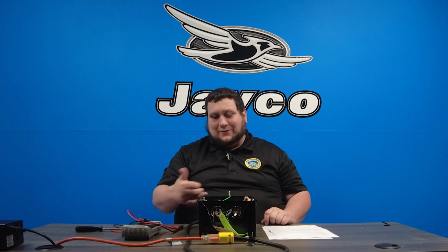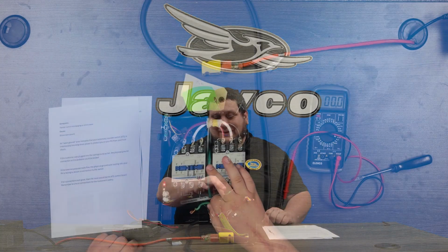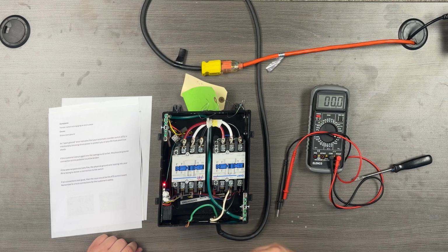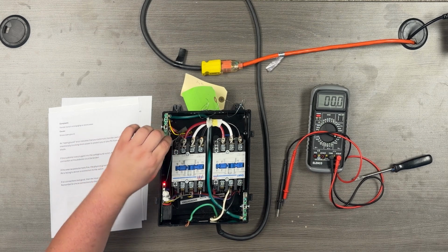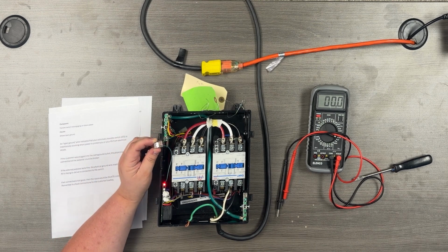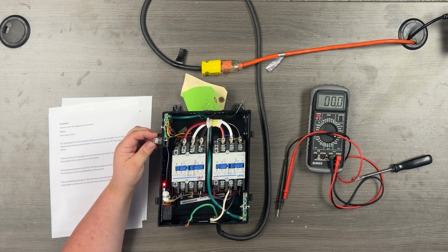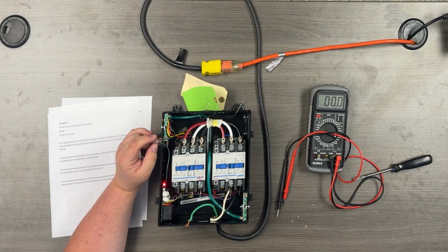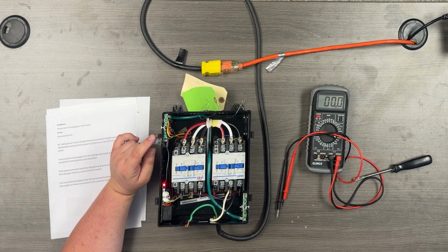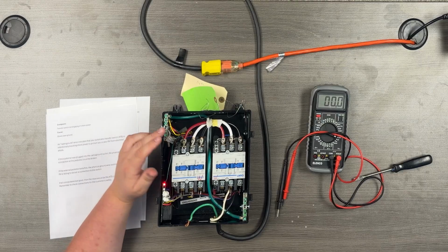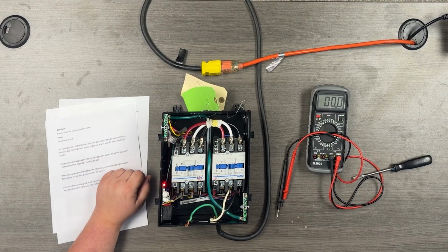So please, do not play around with pressing down the contactor while it is active and while you're trying to get power across. Now sometimes the fault is not going to be quite as obvious as my ground being loose all the way up here like that. Sometimes it can be as simple as what I think was actually the case with this particular transfer switch. My little Wago right here, this side of it was not fully seated, so it may have had an intermittent ground fault because of that cable not being completely seated.